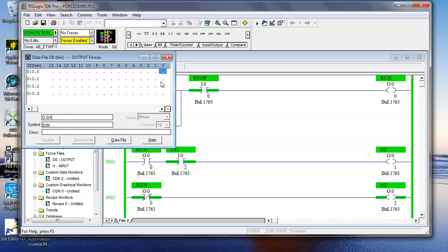But it's great because you might have a PLC over here on the left-hand side that you're trying to develop a program for, and you don't have any push buttons to it yet. You're just trying to program it. Well, you could simulate these inputs all you want to make sure your logic works right. Now that's really great. If you force them in an active situation, you have to be really careful and make sure that you know the consequences of forcing that thing, right?